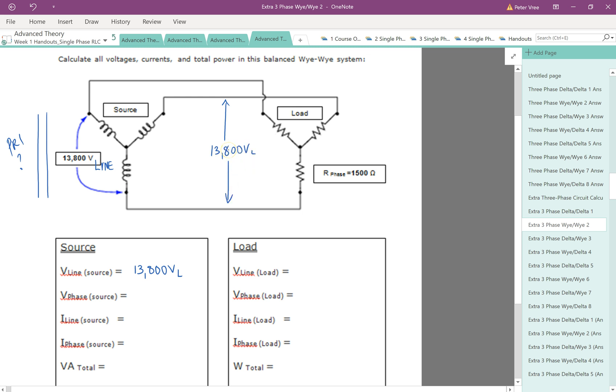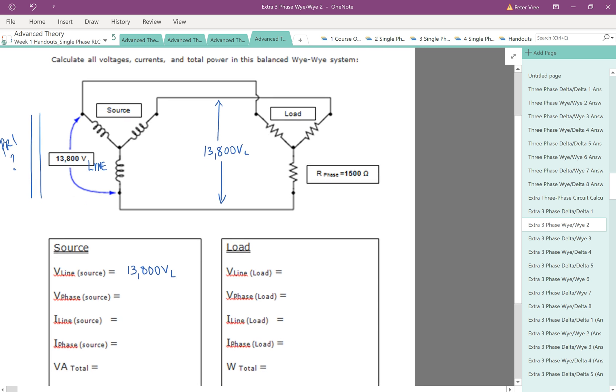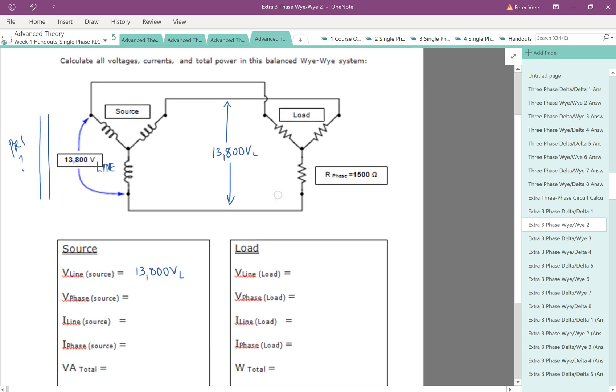But just be careful with this one. Don't get lulled into the fact that we have 13.8. And on the previous example we had 13.8. The phase value right here is going to be root 3 less. So we've got to take 13,800 and divide it by root 3. So let's start off doing this. Because these guys are the same. That was step one.